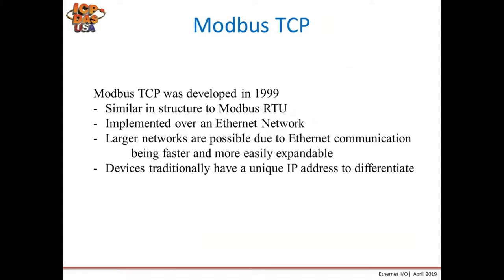Modbus TCP, however, was developed in 1999. It's similar in structure to Modbus RTU in that you can create similar commands and requests, but it is implemented over an Ethernet network, which makes it much more easily expandable, easier to build larger networks, and much faster than serial communication. Devices traditionally have a unique IP address to differentiate them, as opposed to a unique Modbus ID which limits devices to 255.